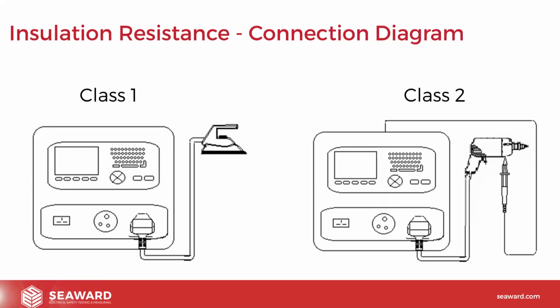In terms of quick connection diagrams, you'll see on screen here. For a class 1, as we've said, there's no need for any additional probes. Everything is measured between the internal conductors of the device we're testing. So the live and neutral are used to output the voltage, and then the earth cable is used as a measurement probe to pick up any earth leakage flowing back into the device that is then measured by the tester.